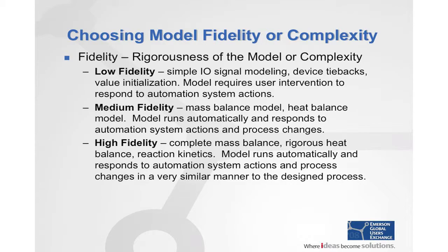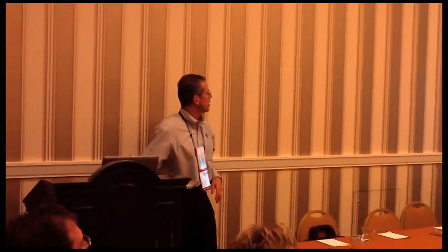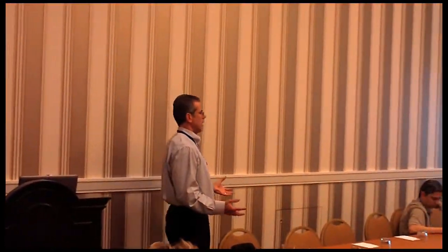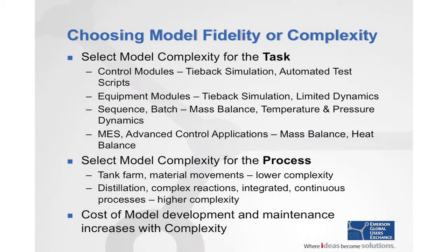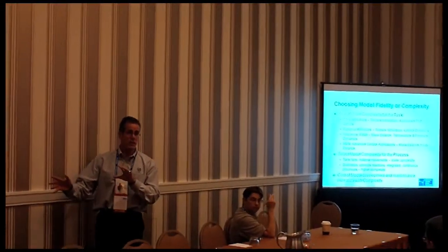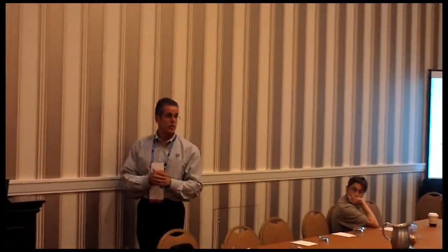High fidelity models require you to add in your individual thermodynamic properties. It's very important to fit the level of complexity of your model to the task. As you get more advanced in the parts of the control system — all the way up to advanced control and MES integration — you'll need more complexity in your simulation. That said, for most control system testing, even advanced control strategies, medium fidelity with good mass balance and heat balance is all you need. If you invest more than that, you may not be getting the results you need out of it.